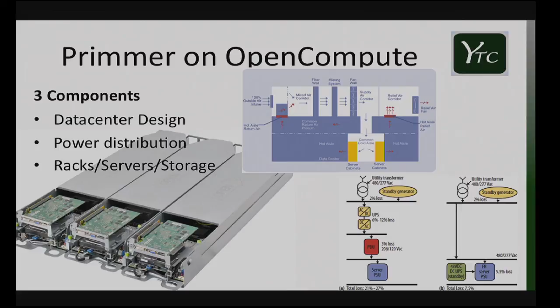Then there's the data center design, which is what everyone was excited about: an open air exchange. Fresh air is blown in through atomizers that mist the air, so the warm air gets moist and cooled passing through the misters. It comes into a cold aisle, blows through the machines, and exits - one pass, never reused. Others, like Google, use the giant warehouse method, a closed loop that doesn't spray air directly, but runs sprayers outside with a cooling coil bringing cool air in.